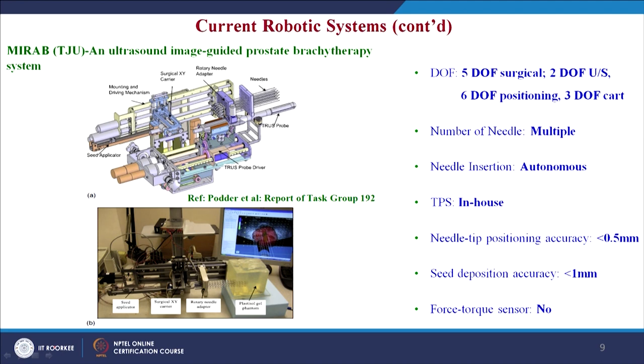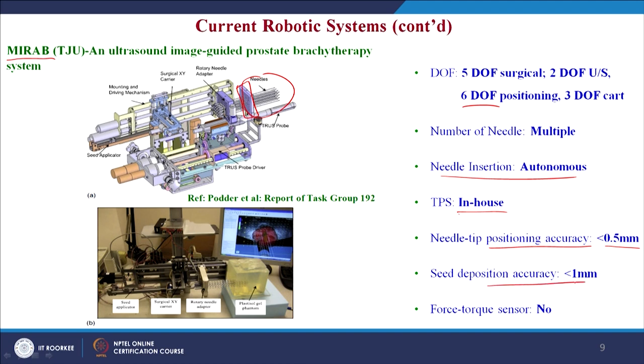Then comes MIRAB — the Multichannel Image-guided Robotic Assistant for Brachytherapy — also developed in the Department of Radiation Oncology at Thomas Jefferson University. It has 6 degrees of freedom and supports multiple needles inserted in parallel using a template for better placement. It has an in-house treatment planning system, autonomous needle insertion, needle tip positioning accuracy less than 0.5 mm, seed deposition accuracy less than 1 mm, and is not equipped with a force-torque sensor.